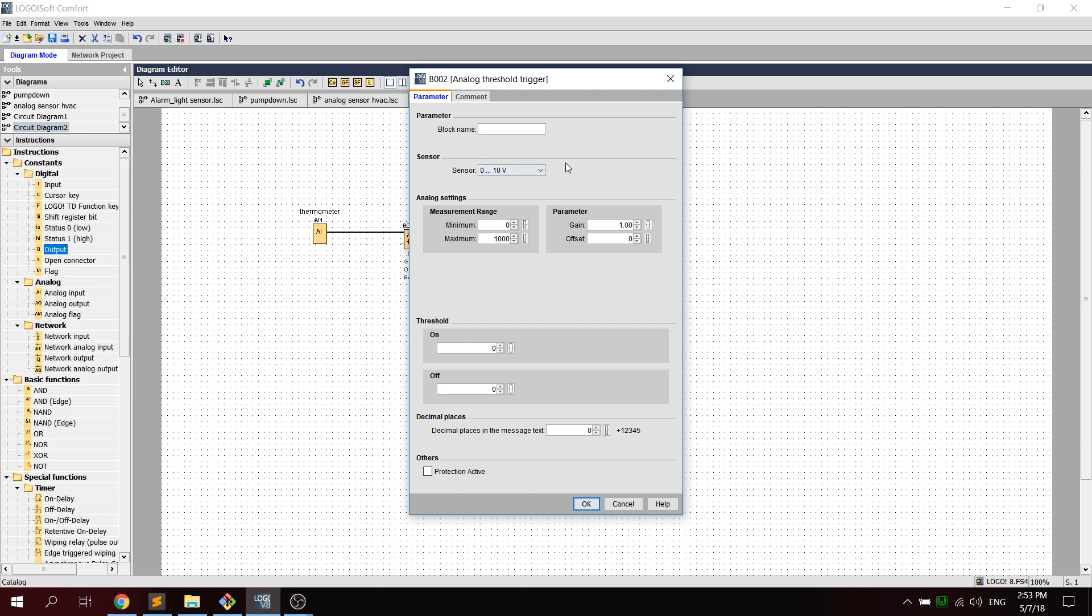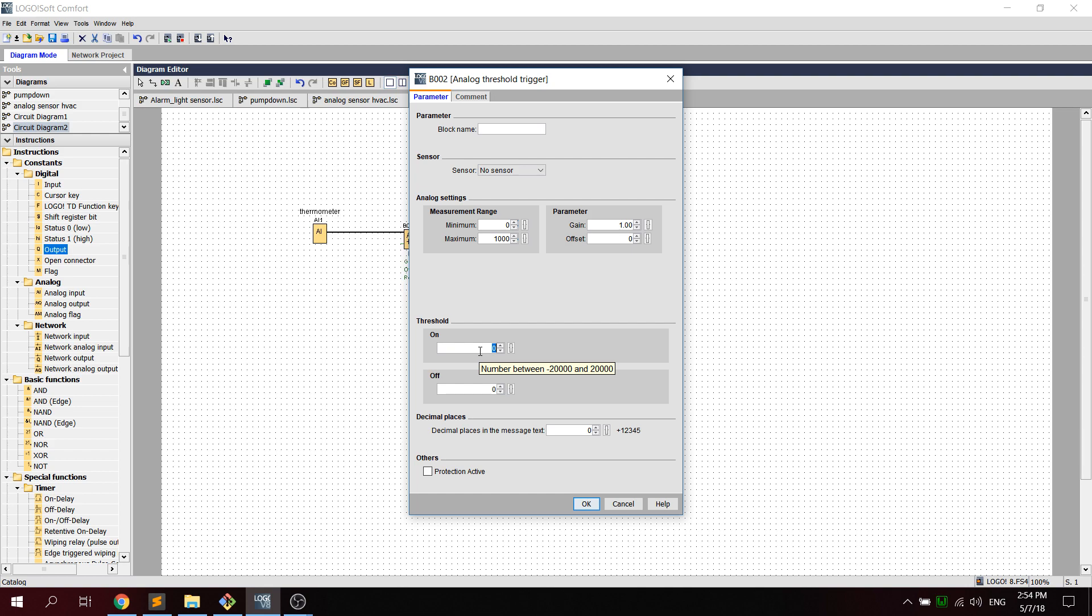So we click here and we go on no sensor, and we go into the threshold. We put the on as, you see, it could be any values. You could put 23 to come on at 23 degrees Celsius and come off at 21 degrees Celsius.